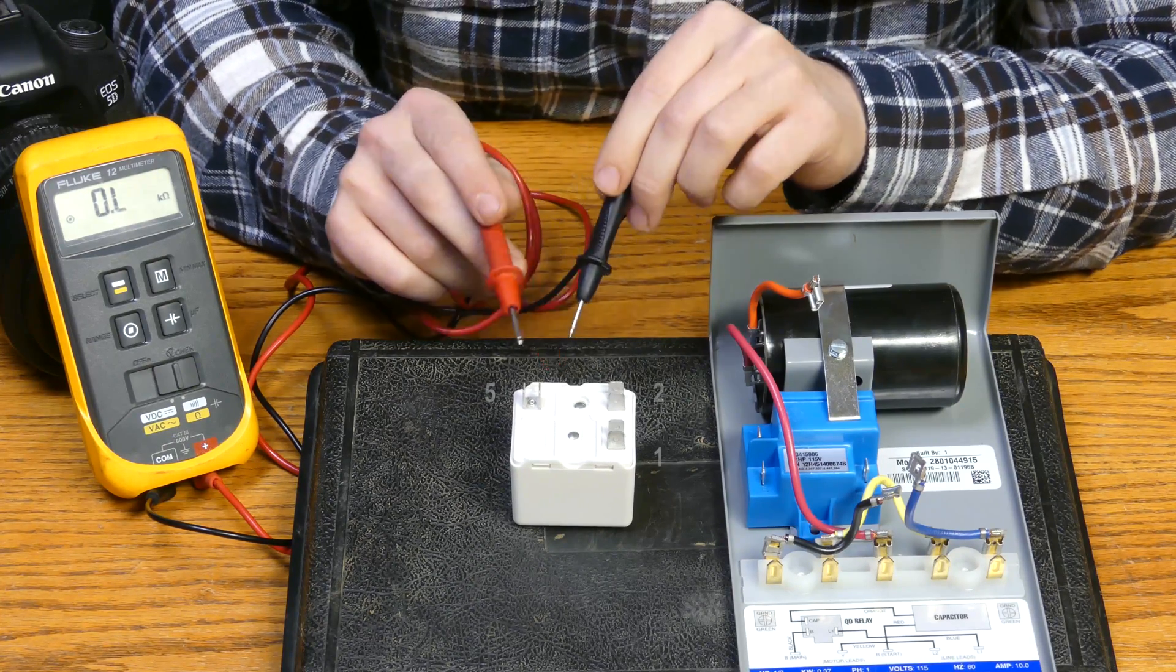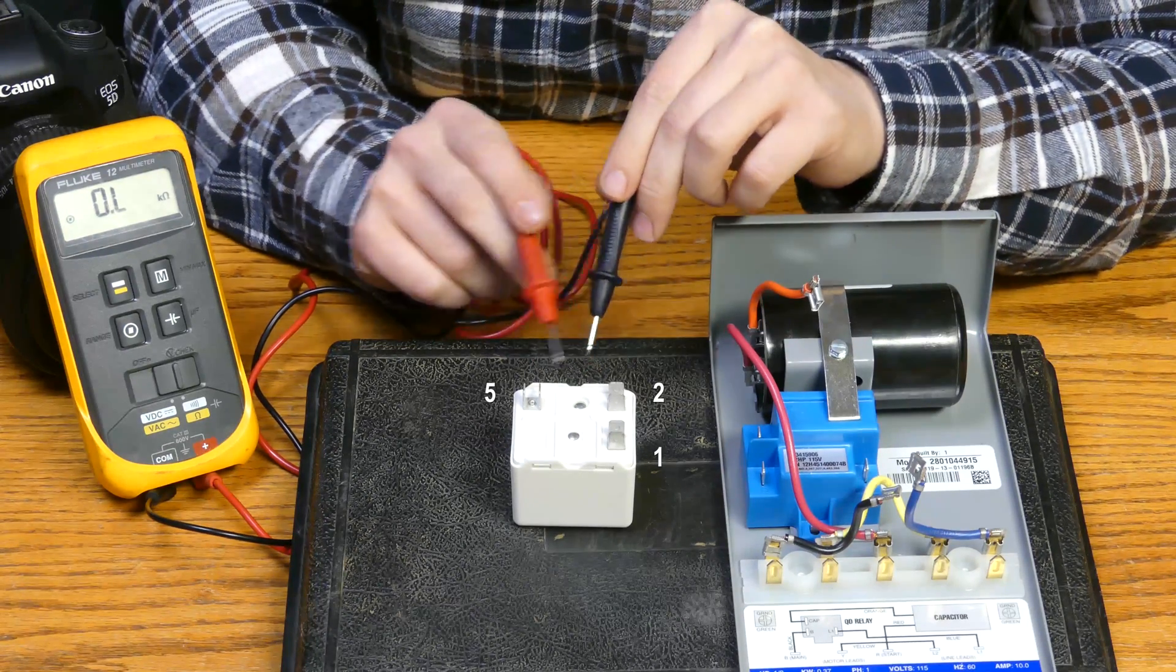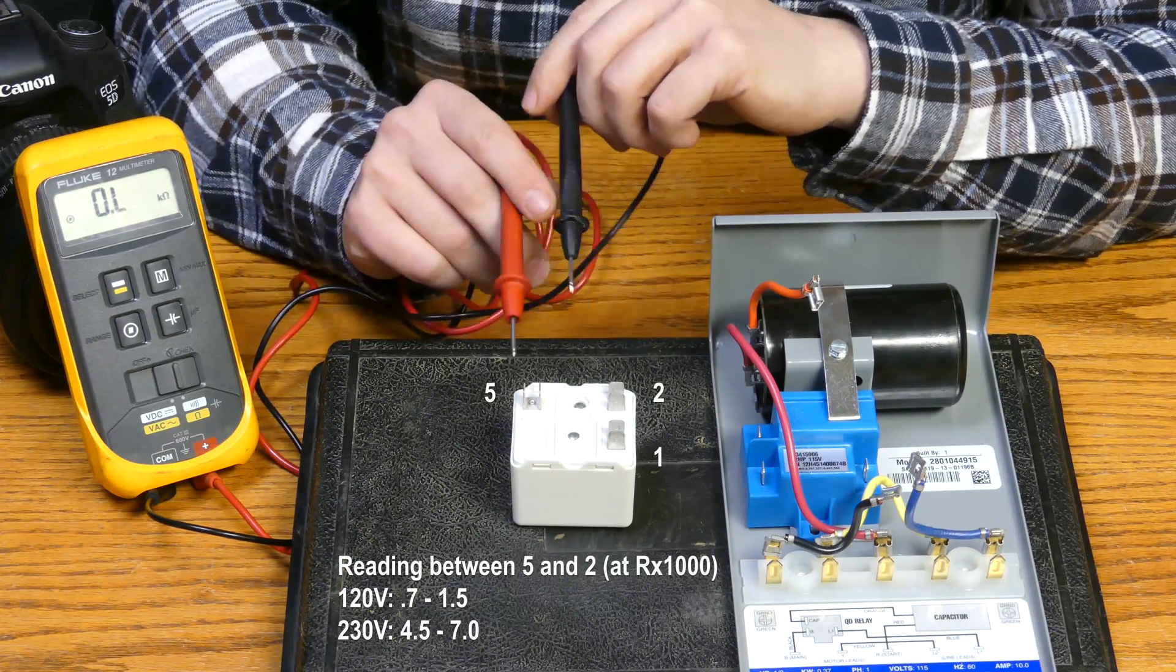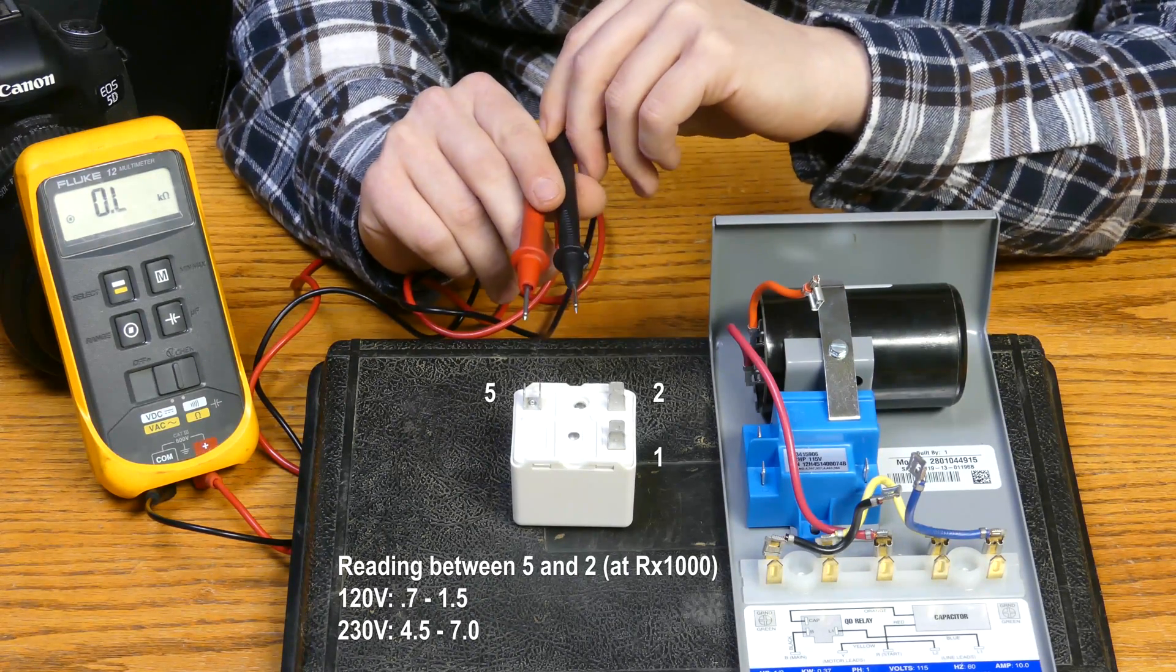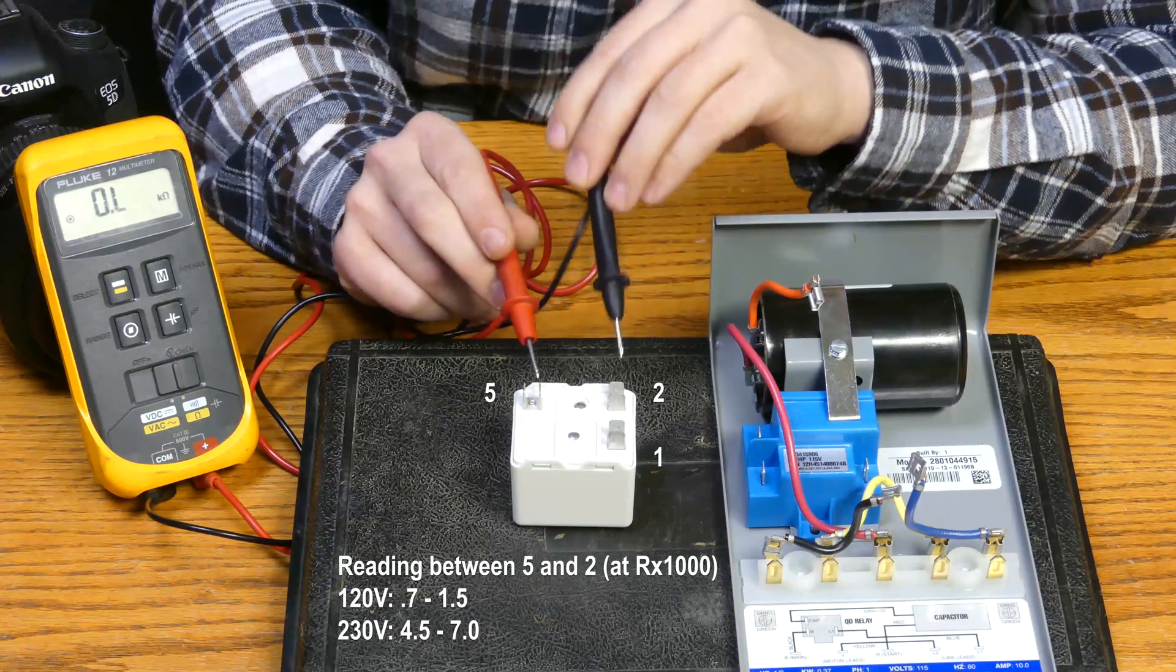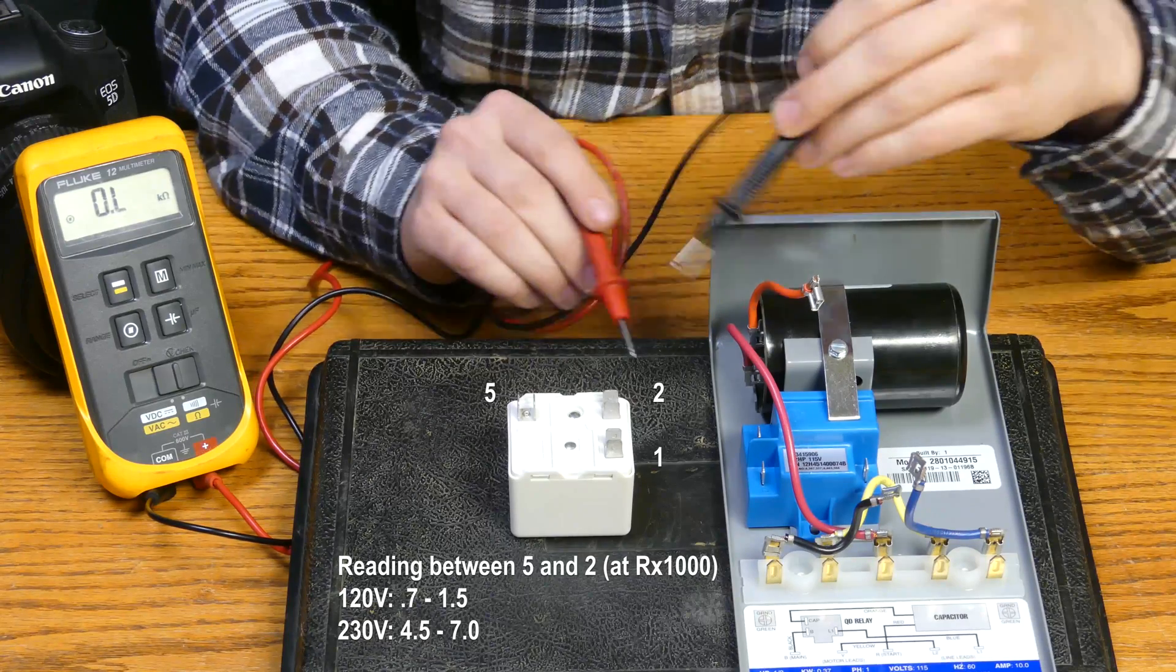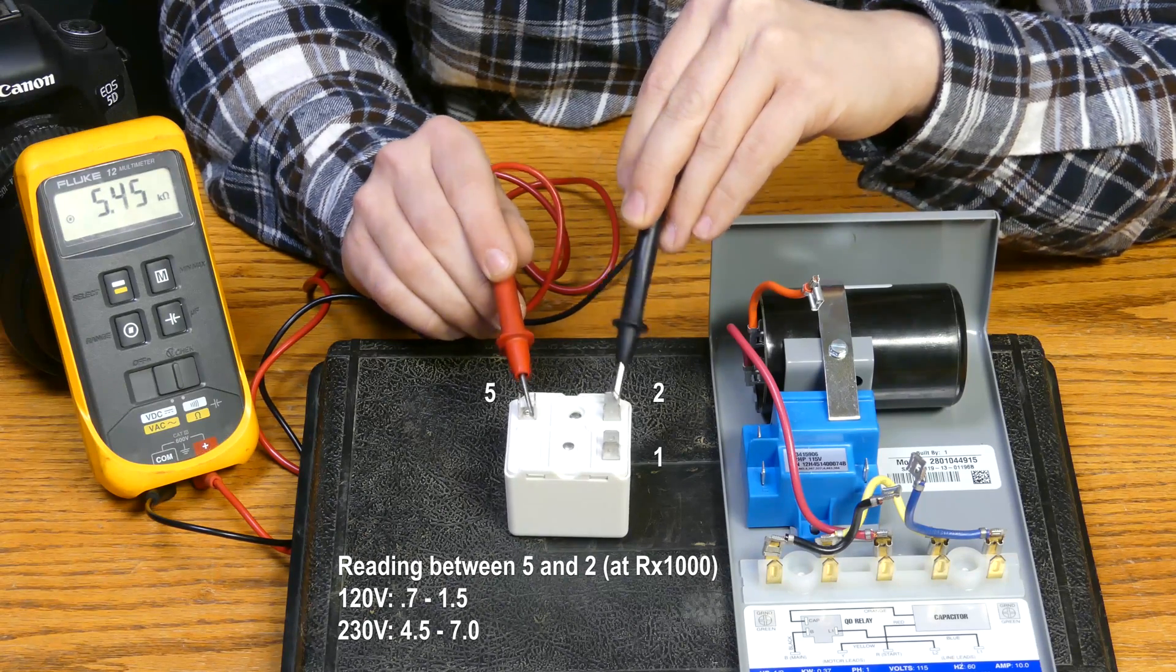So we're going to first start by testing this one here, and we're going to test between number five and number two. What we're looking for here is a number on 120 volt systems between 0.7 and 1.5, and then on 230 volt systems we're looking for a number between 4.5 and 7.0. So let's see what we get. 5.45. So we're right in the range, we know we're good there. So just remember that's between 5 and 2 and we're looking for that number.